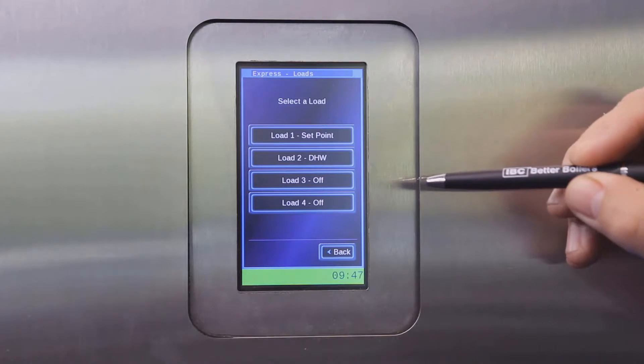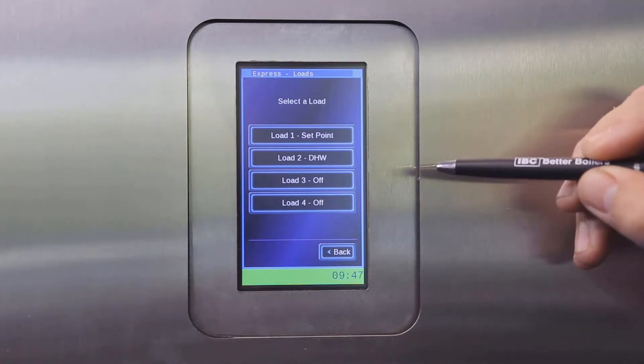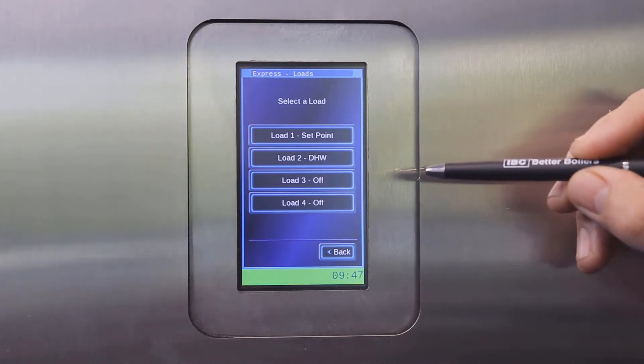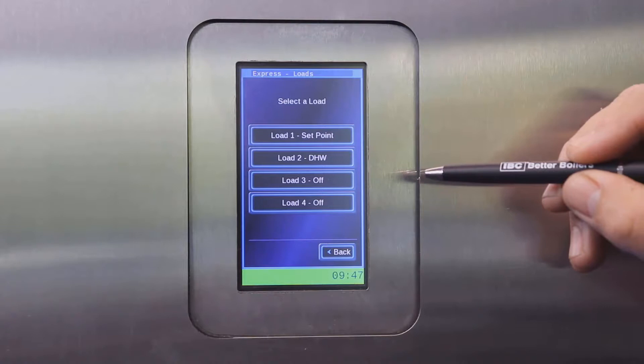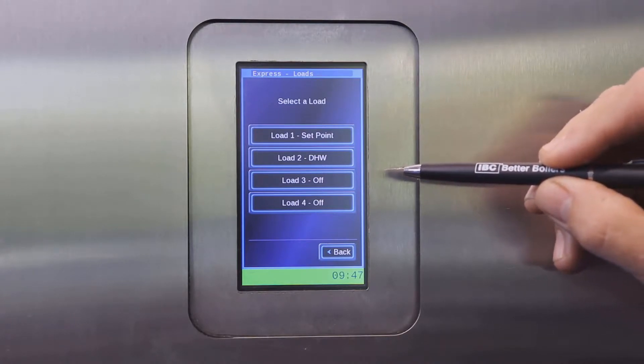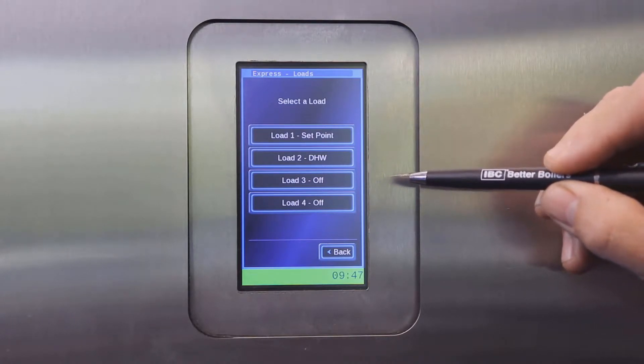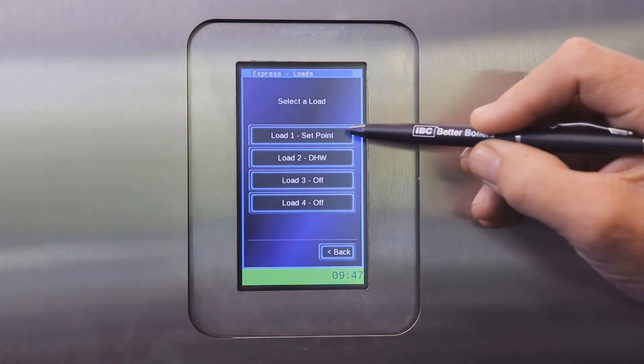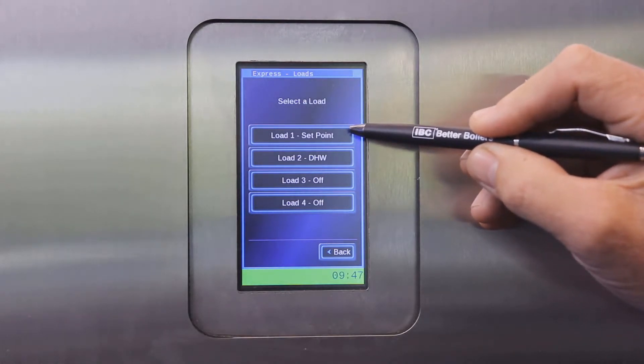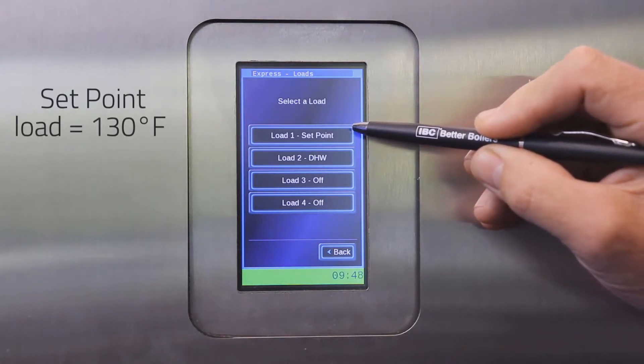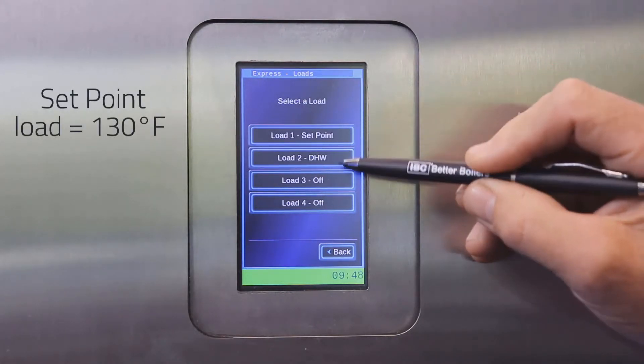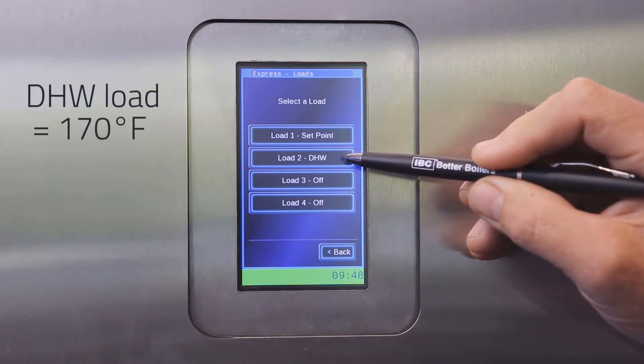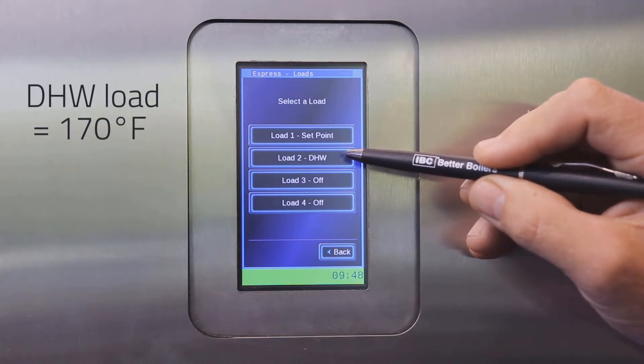Let's look at setting up one of the loads on the SL G3 series boilers as a zone of another load. In this particular case, we have a setpoint load set at 130 Fahrenheit and a domestic hot water load with a setpoint of 170.